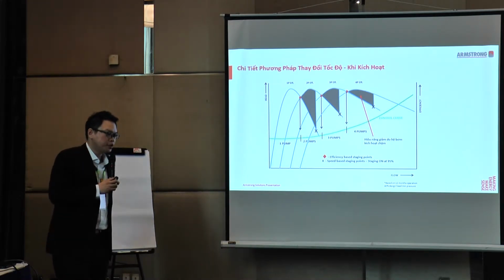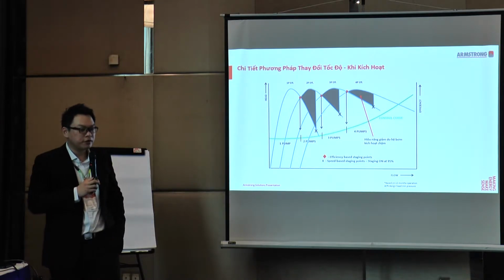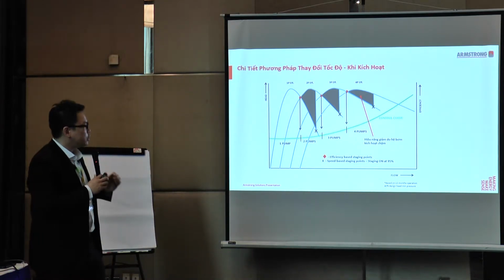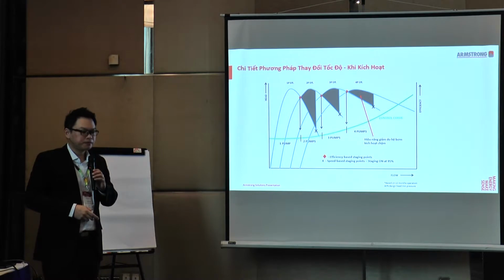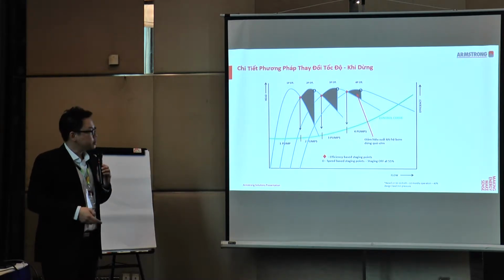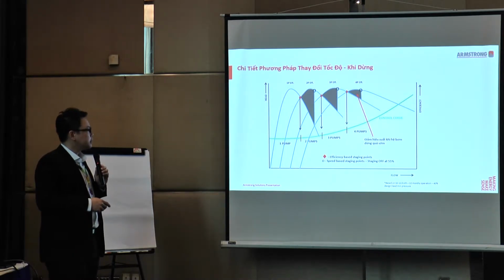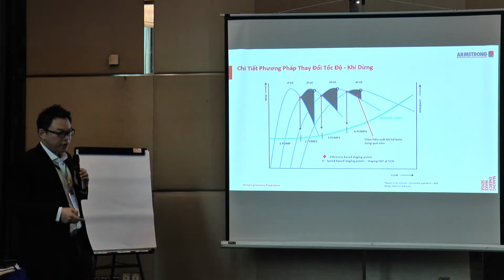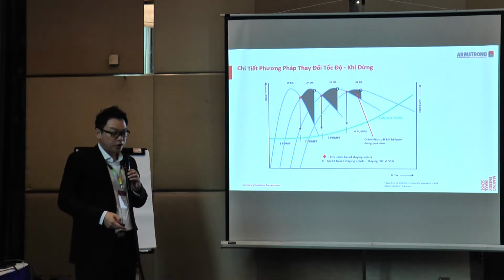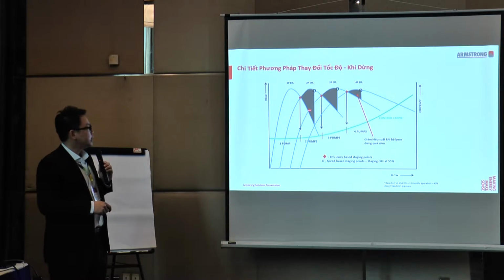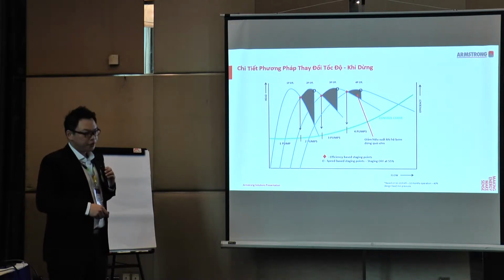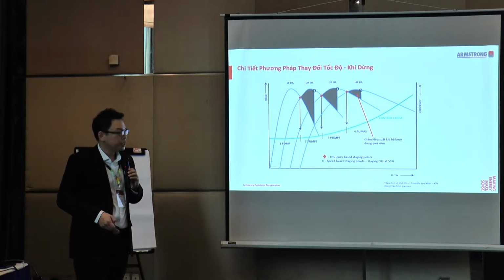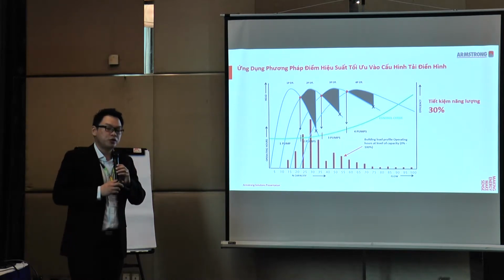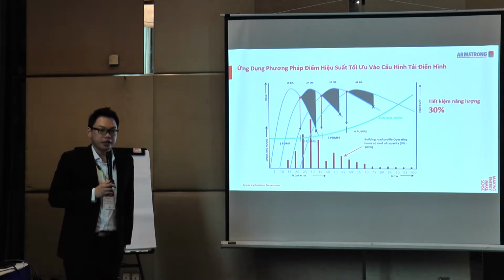Efficiency in the plant room is very, very critical for the overall building performance. Next, when it comes to staging off, the speed-based approach is also staging off too early. This shaded area shows you the loss of efficiency due to staging off too early.